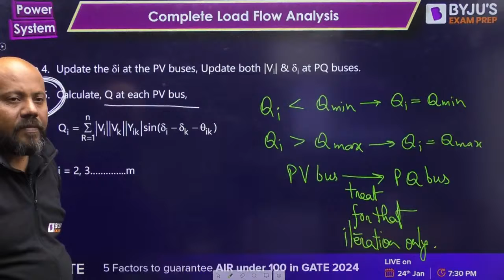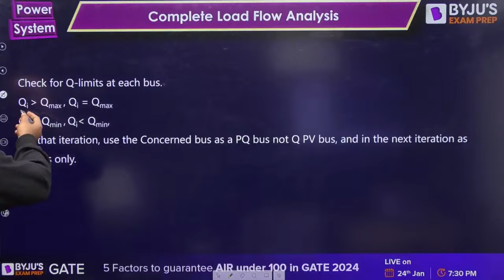For that iteration only. So check for the Q limits: if Q is greater than Q max, Qi is Q max; if Q is less than Q minimum, Qi is equal to Q minimum. For that iteration, treat the concerned bus as a PQ bus, not the PV bus. And in the next iteration, again treat it as the PV bus only.